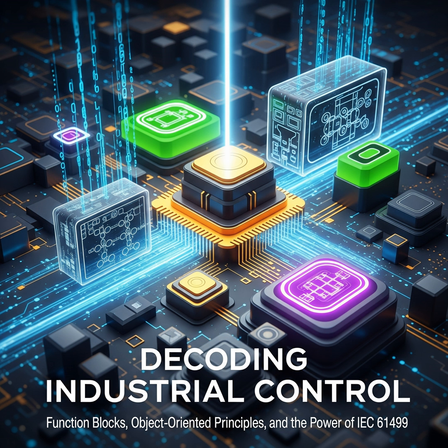So you can change the running system. Exactly. A management function block could, for example, trigger a cold start or a warm start of a resource, or maybe dynamically add or remove parts of the control logic without having to shut everything down. Wow, that's powerful. It really is. It means that whole object-oriented idea doesn't just stop at the initial design. It extends right into the management and maintenance of these functional units while the system is live. Okay. It's about enabling these complex systems to be dynamic, to be adjusted, updated, maintained without always needing a full stop, which is essential for the kind of agile, responsive manufacturing and infrastructure we need today.